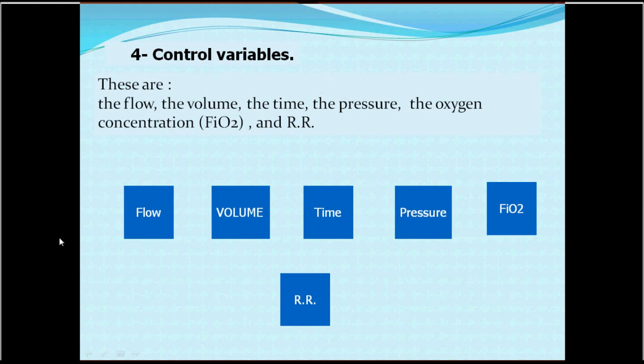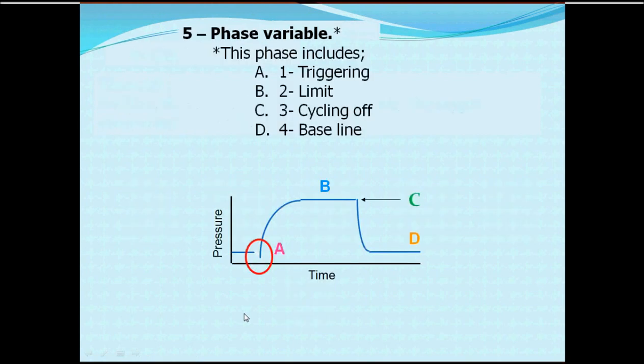The fourth component is control variables. Control variables refer to the physical characteristics of the delivered breath. Delivered air has a volume, a flow, and is delivered in a certain time, developed by certain pressures, with a certain FiO2 composition. All these data are repeated at a certain frequency per minute — the respiratory rate. So when we talk about control variables, we mean the physical characters of the breath: volume, flow rate, time, pressure, composition, and respiratory rate.